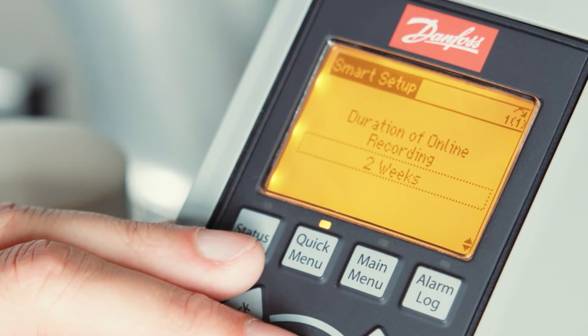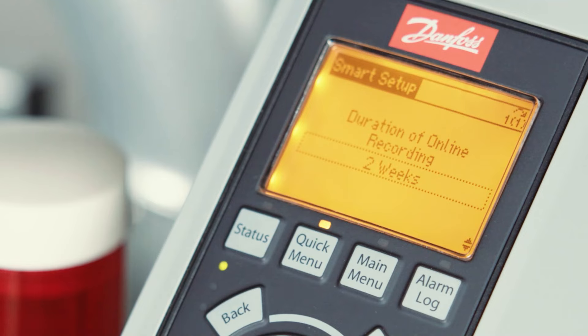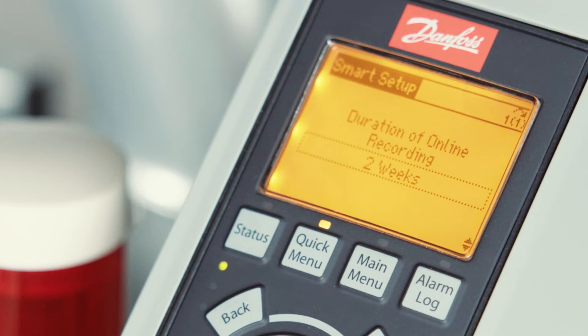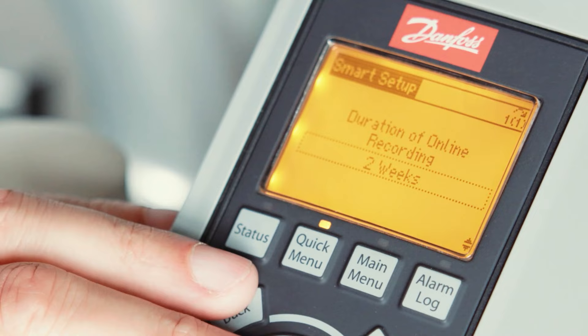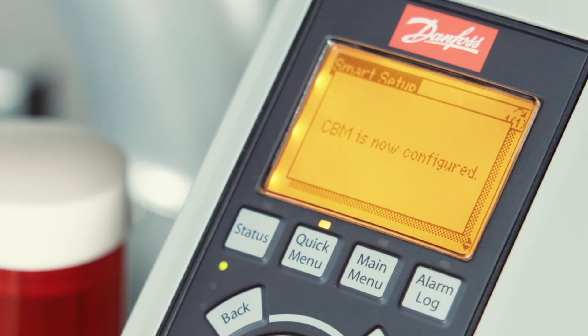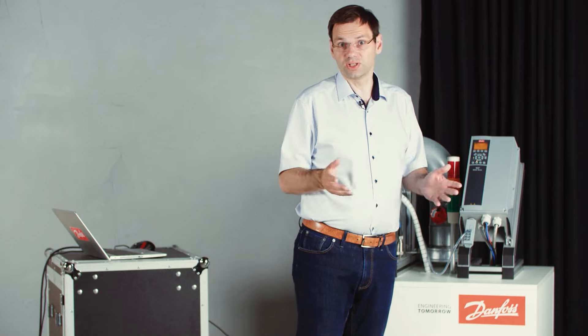Leave the default value and the next question is about the duration of the online recording. When using Smart Start with Easy CBM, the baseline is generated online and you tell the drive the learning period — in this case, two weeks. The drive will learn the normal values during operation and generate the baseline at the end of two weeks. After that, it will automatically generate thresholds and start the monitoring phase. Once this is done, CBM is configured — you are ready to go.